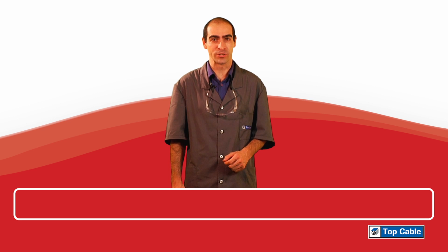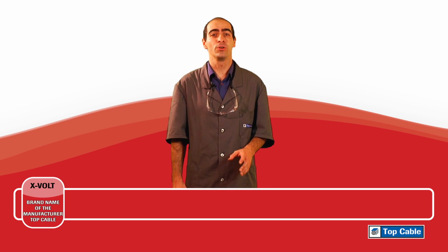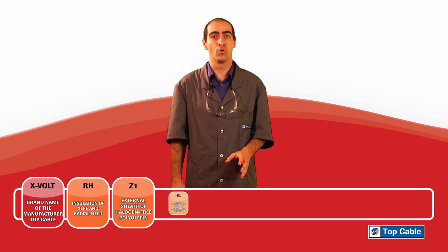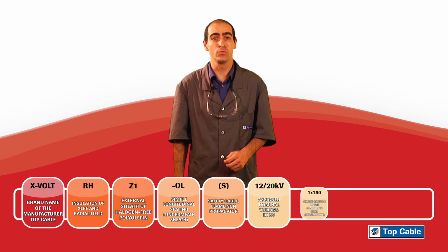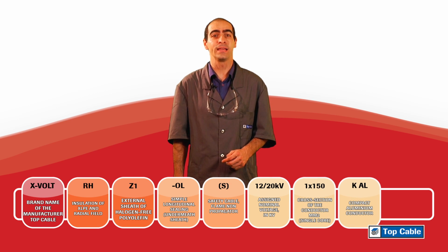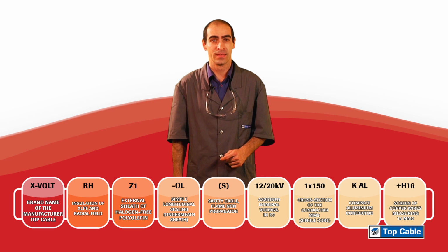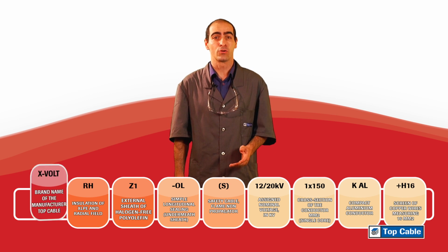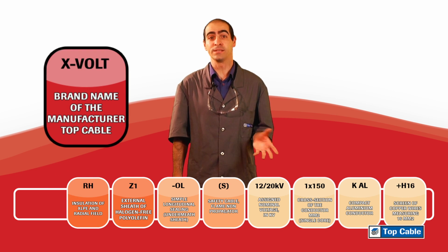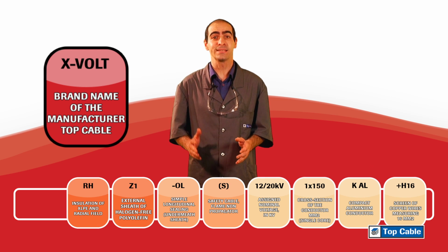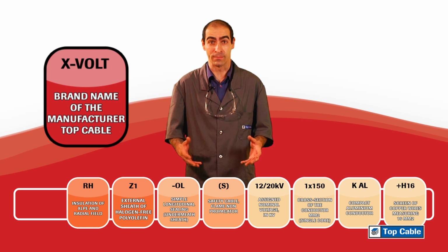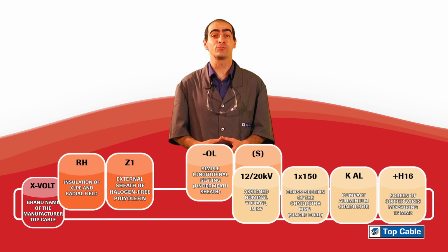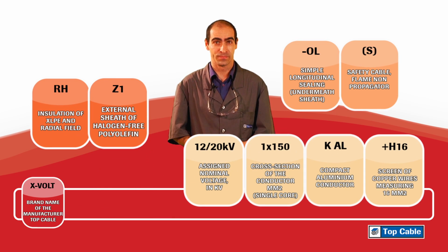Medium voltage cables also have a name and description code according to the standard. Xvolt RHZ1 OL S 12/20 1x150 KAL plus H16. Xvolt is the brand name of the manufacturer, in this case TopCable, for medium voltage cables. We have divided the detailed explanation of the medium voltage cable designation into 3 blocks.